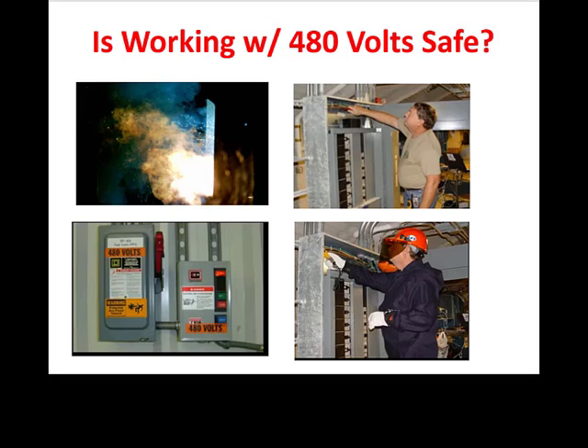Live electrical work must not be allowed, and lockout-tagout is required when performing any type of electrical work. The photo at the top right shows what unprotected live electrical work can look like. I advise you not to put yourself in a situation similar to this, since this panel is most likely 480 volts or more. The only exception to this is when troubleshooting with a voltage meter to determine the problem. Troubleshooting with a voltage meter is live electrical work when an arc flash hazard exists, and appropriate PPE must be used as shown in the photo at the lower right. Once the problem is found, lockout-tagout must be used before making repairs.